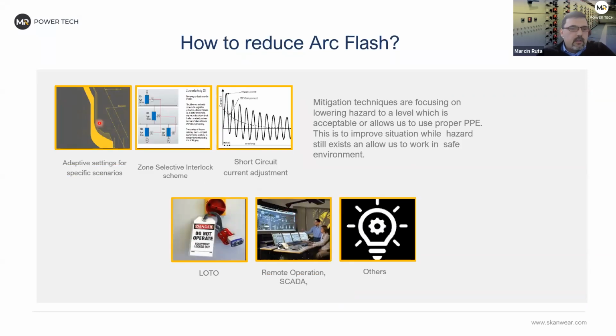The second group will be adaptive settings. So that's specific for a scenario, and we'll talk about it. There's also selective interlock. Short circuit current adjustment is a very specific topic, not always utilized. Lockout, tagout, of course, remote operation, remote tracking, SCADA operation, that's all nice to have. And there are some other tailor-made solutions, very specific for some specific projects.